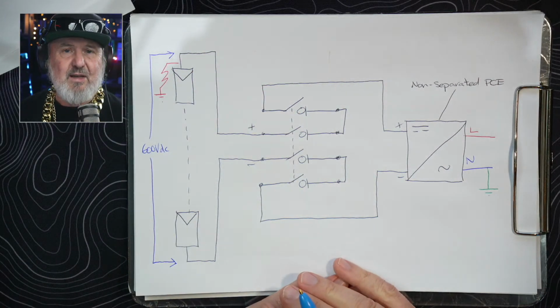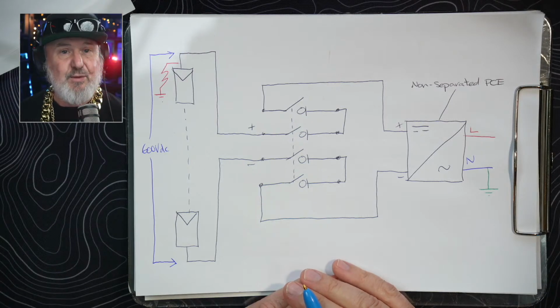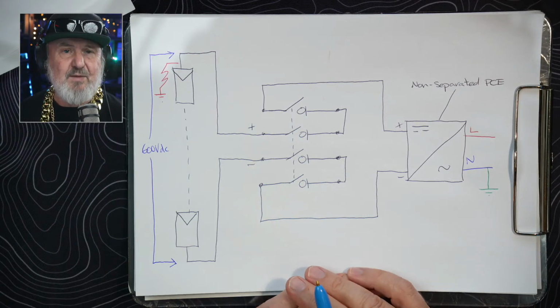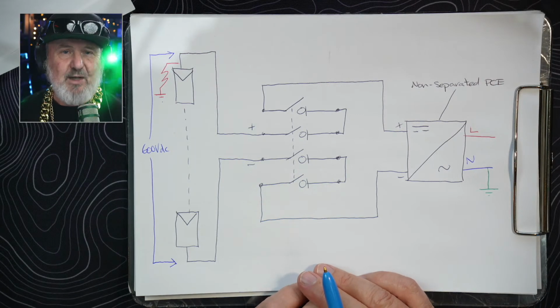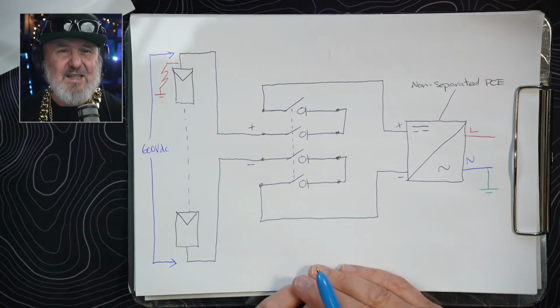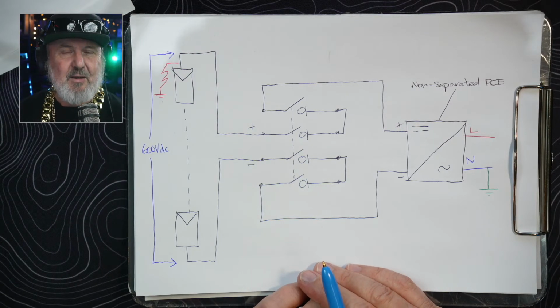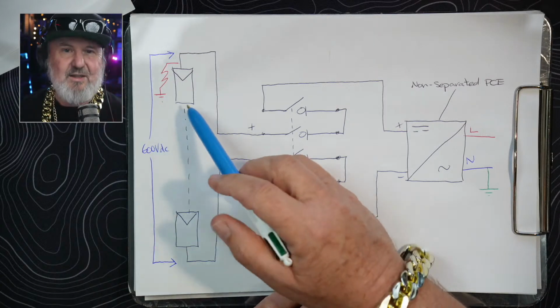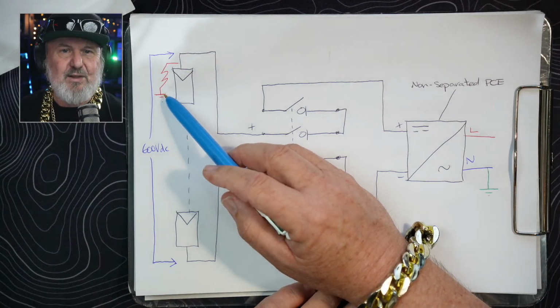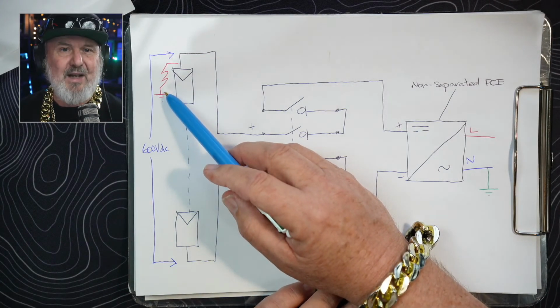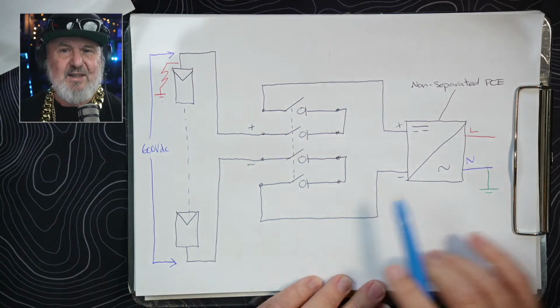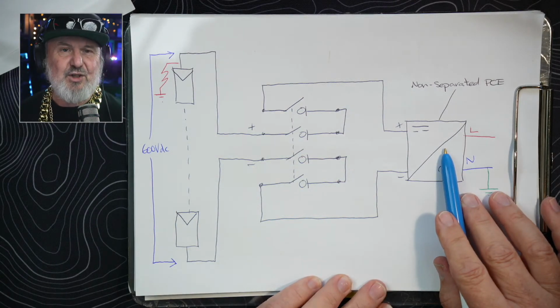Now, how do we get that short to earth? It's a requirement to have equal potential bonding of array frames. All conductive parts of a PV array, including the module frames, must be bonded to earth. So there's a ready path to earth. And you might think, well, it's actually making it easy for a fault to occur. But it actually is helpful when that fault is a relatively weak path, like high resistance. The inverter can detect that fault and shut down.